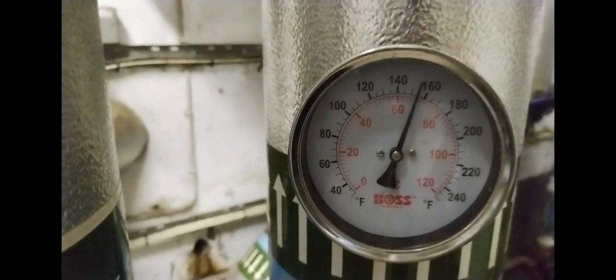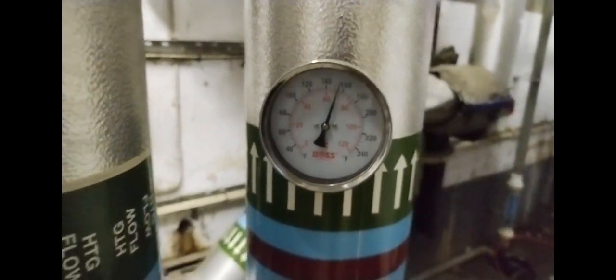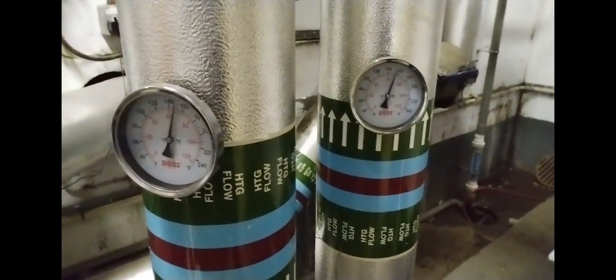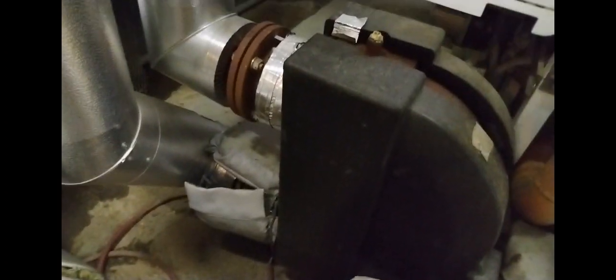I'm checking my temperatures on my boilers before I switch them off for servicing. This is my low loss header. We got about 65 to 60 Celsius on our flow and return.